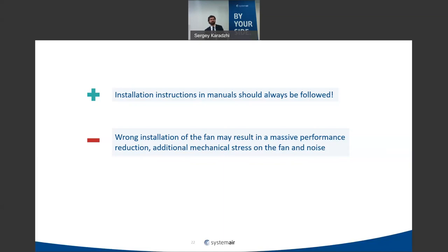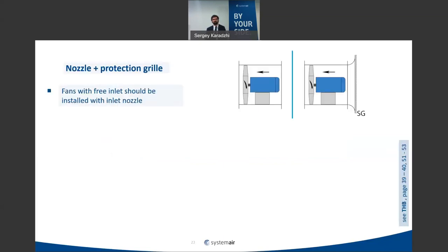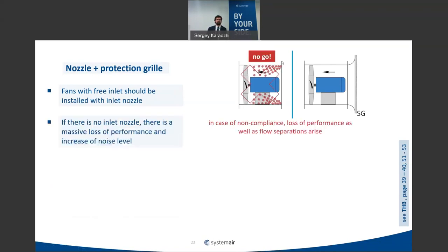For example, for free inlet/free outlet (Category A), you must use an inlet nozzle and safeguard — without the inlet nozzle, you will have flow separation from the fan casing edges, which reduces fan performance. The inlet nozzle itself introduces some losses depending on its radius, but these are much smaller than the losses without it, as confirmed in technical handbooks.